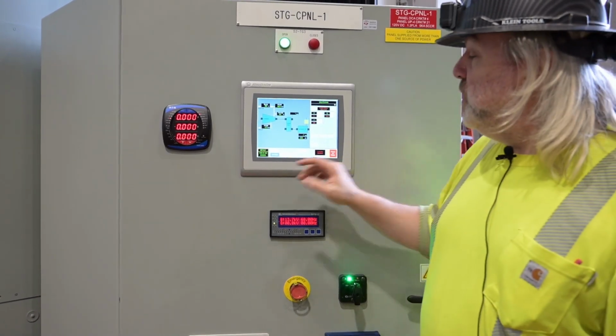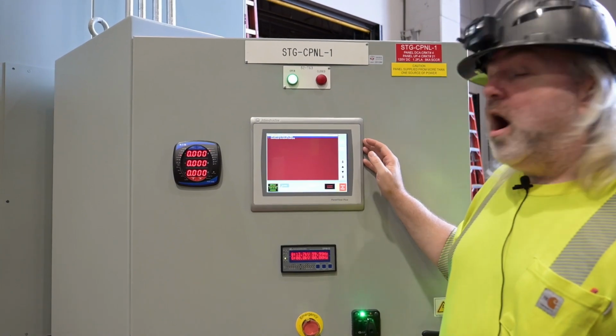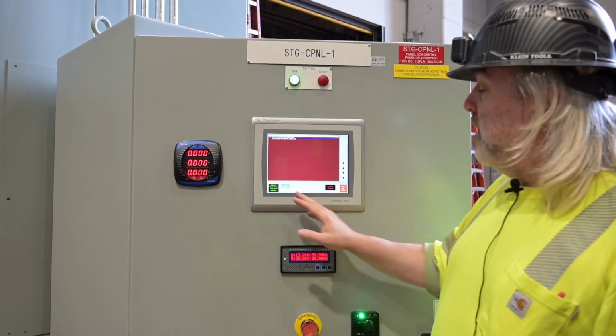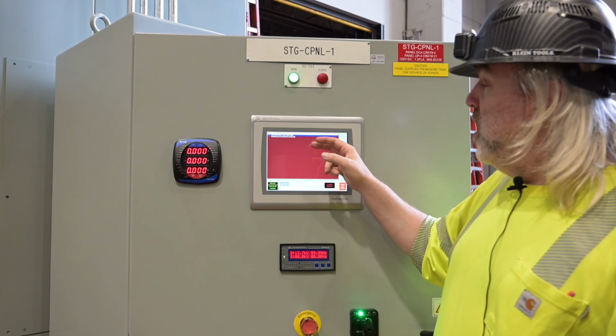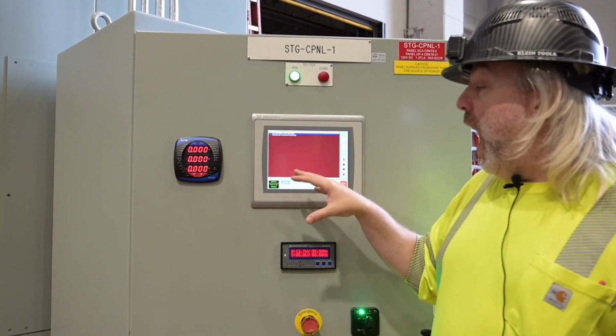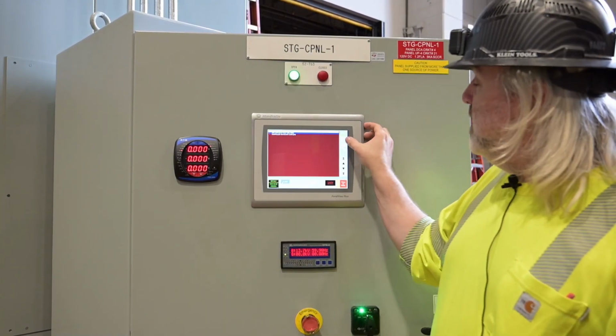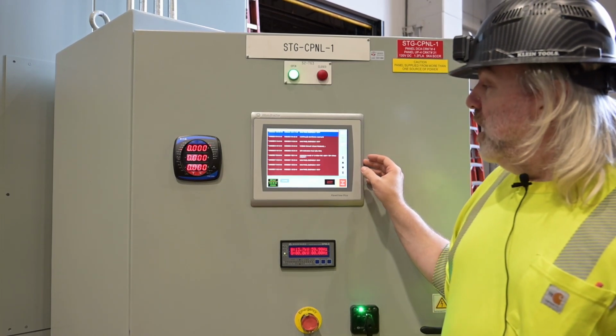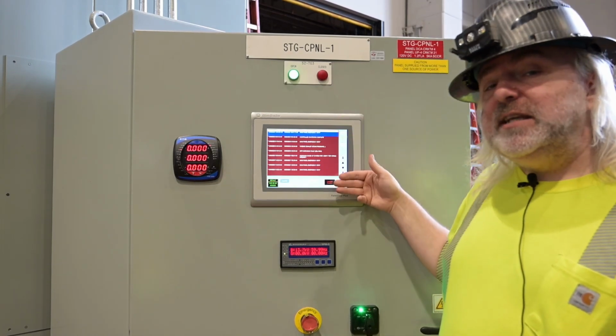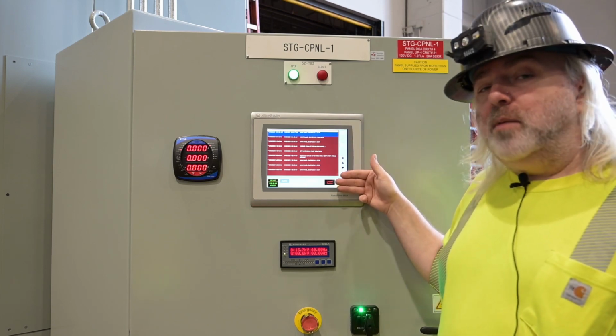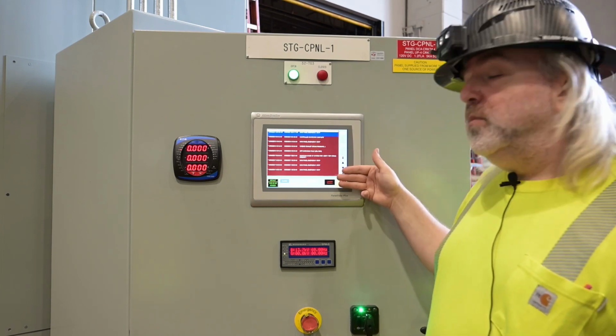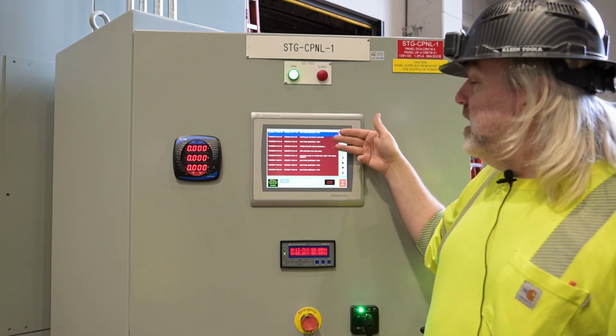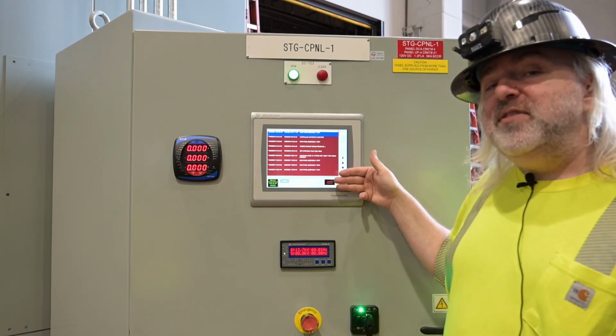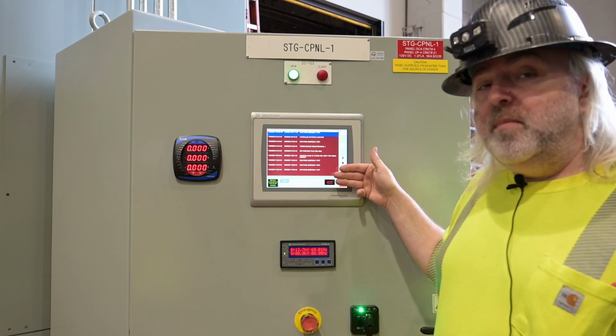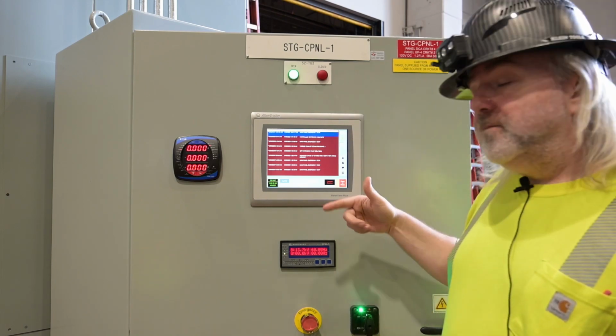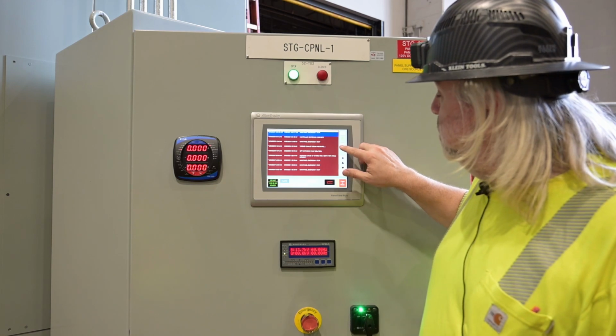On the HMI, we have the following screens available for the operator. We have an alarm area. Under the alarm, we have active alarms. These are alarms that are currently active. We then also have a history. Under the history, we have a list of the last 999 alarms that were set to the machine. These alarms will exist always. Once you reach 999, the next one will bump the oldest alarm, and it will continue to cycle as a circle. We have an acknowledge button.